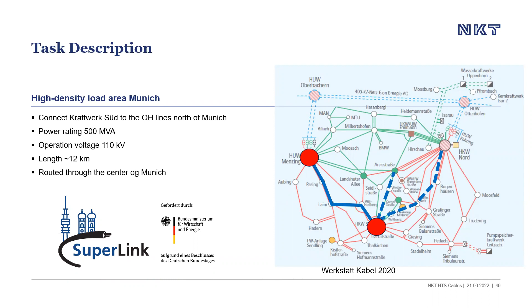So we're looking at 500 megawatts at an operation voltage of 110. One single HTS cable replaces 5 conventional cables, which would require 5 separate routes through the center. Next slide, please.